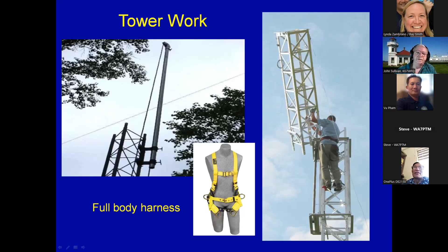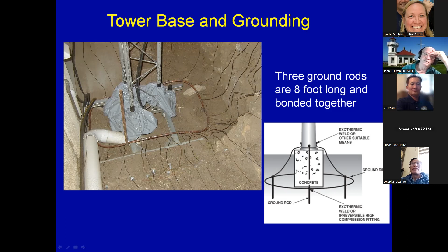This is an illustration of ground rods at the base of an antenna. Each leg of a tower should be grounded, with ground rods that are, again, 8 feet long. You should have several of them, and they should all be bonded together, so there's all a common ground. Because you want to think about that tower sticking up there - it's really attractive for lightning.